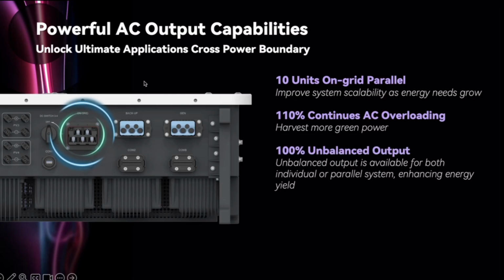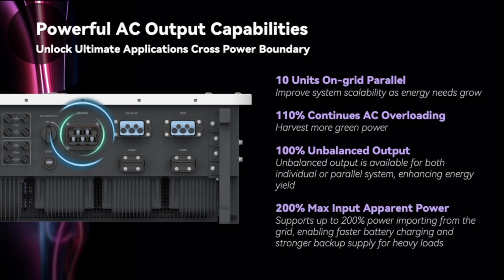And we also offer 100% unbalanced output, which means the inverter can handle the uneven loads on each phase. Whether it is used as a single unit or in a parallel system, it can maximize the energy yield for every situation. And finally, it supports a 200% grid-side apparent power input, so it can import more power from the grid when you need it. For example, support the loads in your house and also charge the battery at the same time.